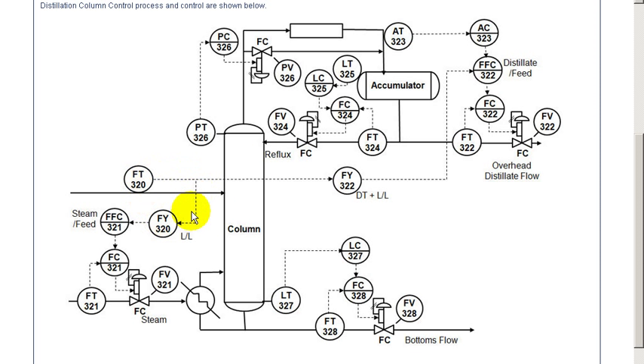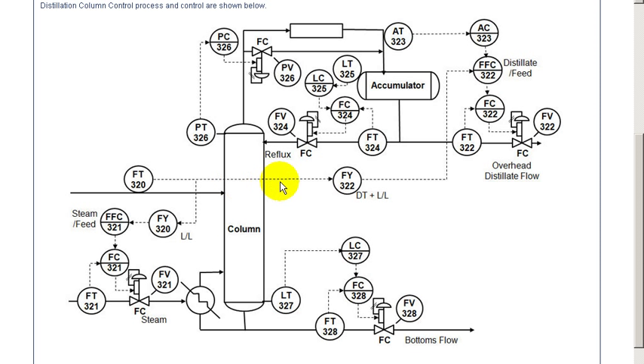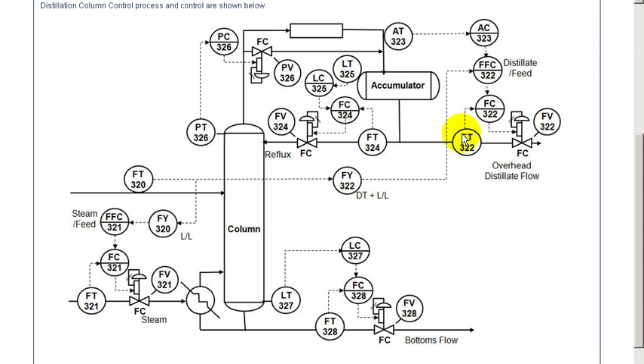Based upon the feed rate, through the use of a steam feed ratio control, the steam demand is being set. Also the feed rate is used after dynamic compensation as an input to the distillate to feed ratio control which sets the distillate feed rate.